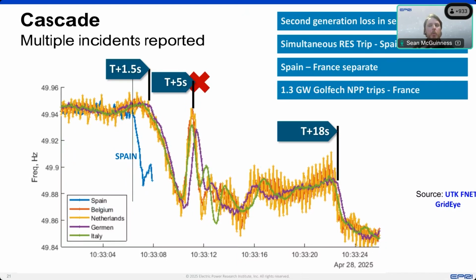We don't have exact clarity on the exact sequence of events. We don't have the information to label each of these individual frequency dips or these oscillations. We know roughly what happened, but we don't know the sequence.